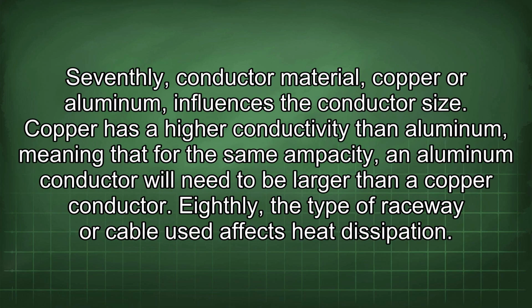Seventhly, conductor material, copper or aluminum, influences the conductor size. Copper has a higher conductivity than aluminum, meaning that for the same ampacity, an aluminum conductor will need to be larger than a copper conductor.